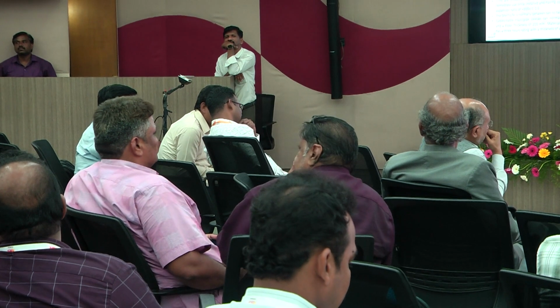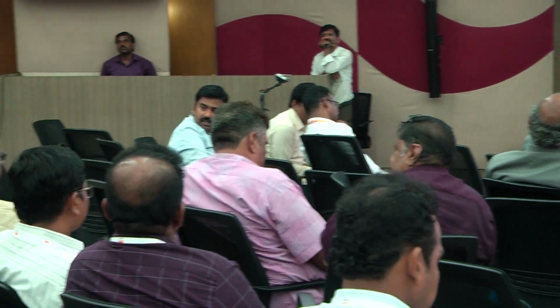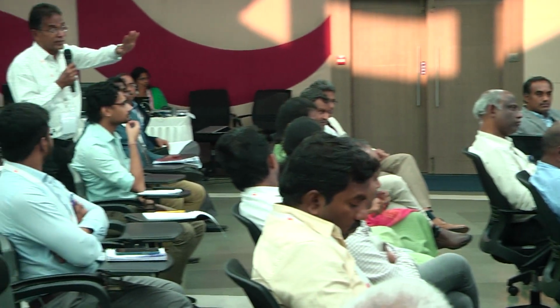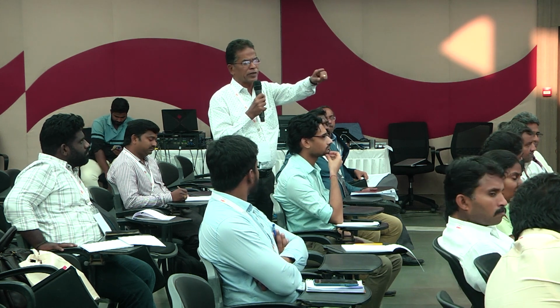No, sir, it is not half the run. The paint coating will penetrate and go to the bottom of the cable also. Moreover, every 14 meters, 1 meter length of cable can be coated. It is enough. Not full length is required. As per the practice, every 14 meters, 1 meter length of cable can be coated. A complete fire barrier is required, 2 hours fire rating, as recommended in the National Building Code.